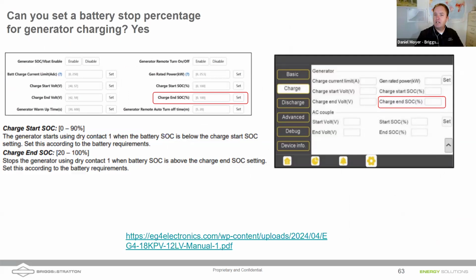One reason I think EG4 is one of the best manufacturers on the market for integrating generators is that 125 amp input on the Grid Boss. But here's the other one. With some of the other hybrid inverters on the market, you can set the start percentage that will signal the generator through a two-wire signal to start, right? Battery is getting low, maybe it's down to 20%. Let's start that generator. Let's use a generator to charge up the batteries and support the loads in the home. Once the battery is full, the generator will shut off. With other inverters, unless you do some advanced programming through the time of use settings, that generator is going to run all the way till it's full. The generator is going to run a long time.